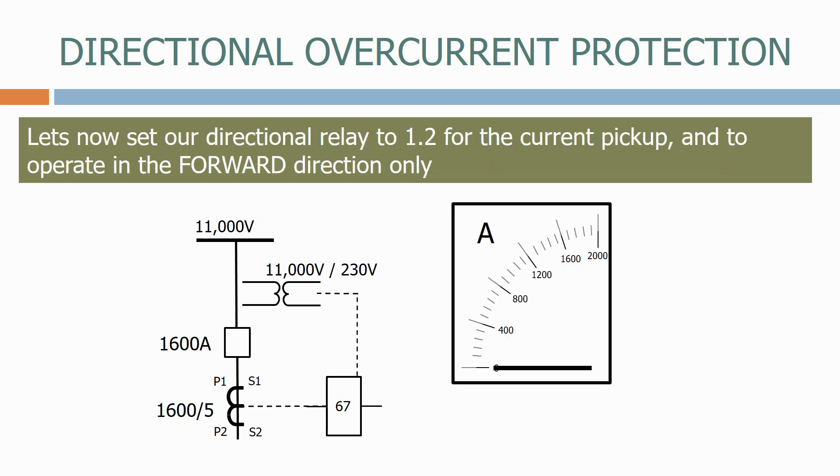Let's now set our directional relay to 1.2 for the current pickup, and to operate in the forward direction only.